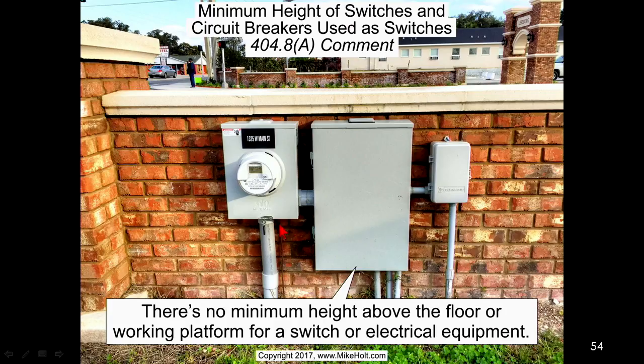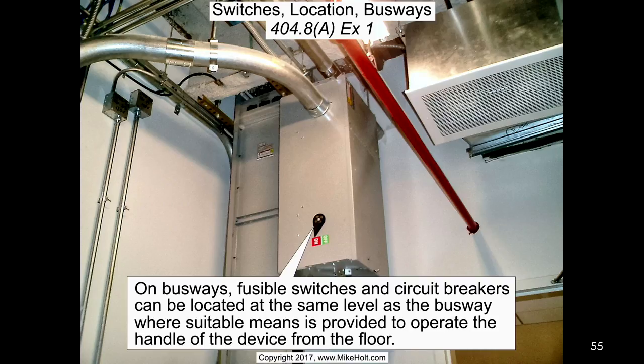So here's a switch. You can have it right on the ground. You can have it placed as low as you want to. Just the maximum height. Busways, there's an exception for busways. Clearly, a busway can't be 6 feet 7 inches, so that can be above that.